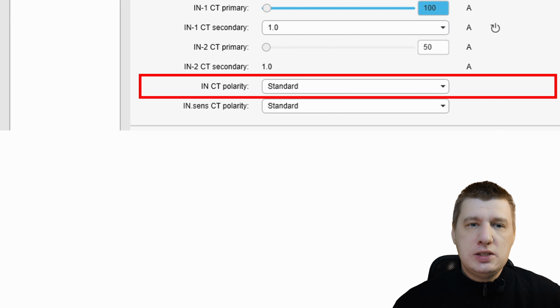We talked about phase CTs, but now we're focusing on the input also known as the residual or earth fault CT input. Getting the polarity right here is the difference between a relay that protects your system and one that trips blindly or fails to see the fault entirely. Let's see what standard means.